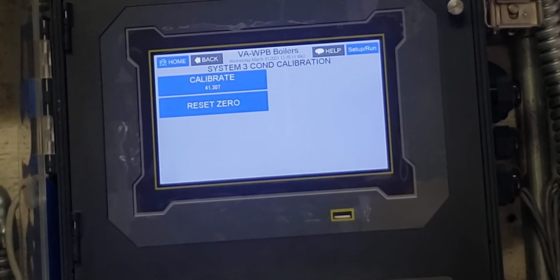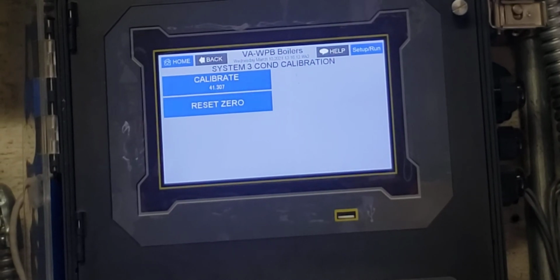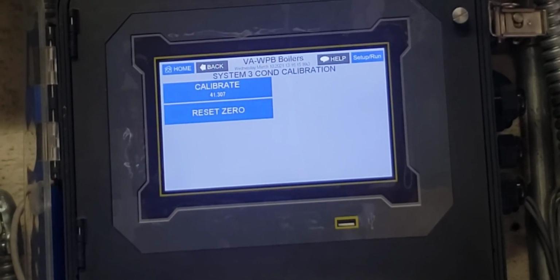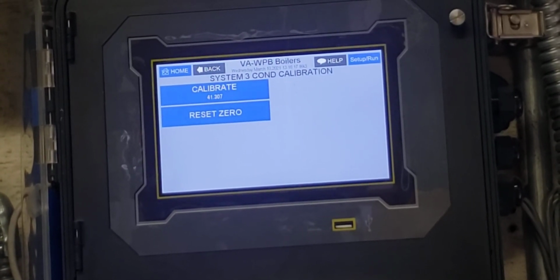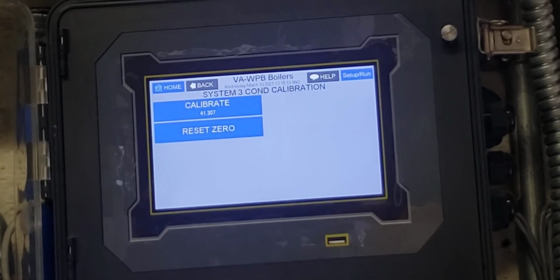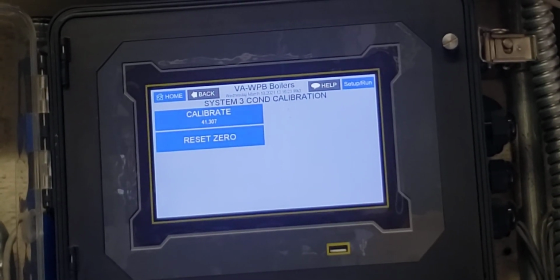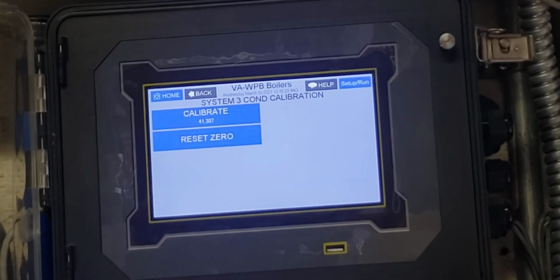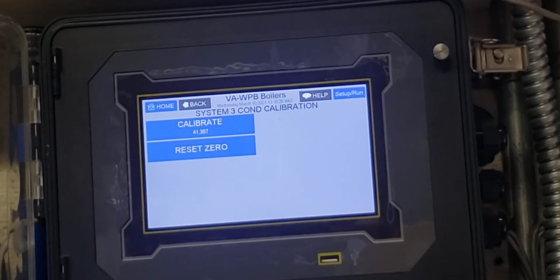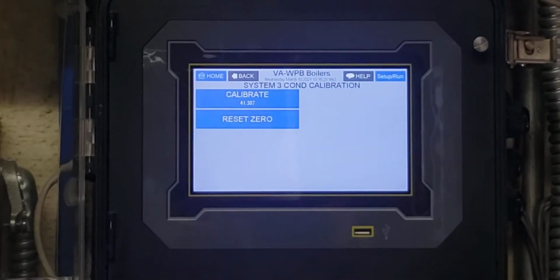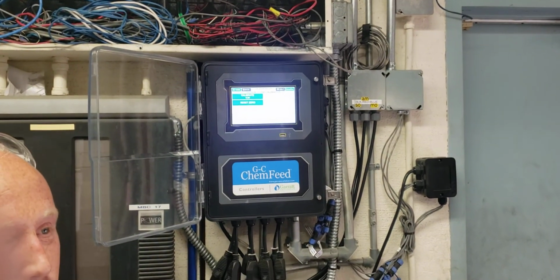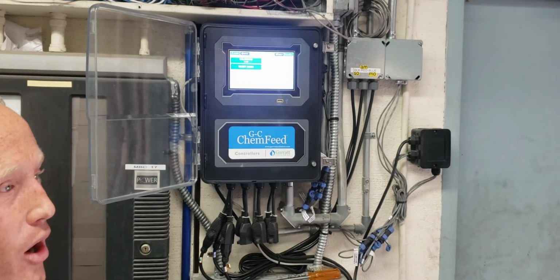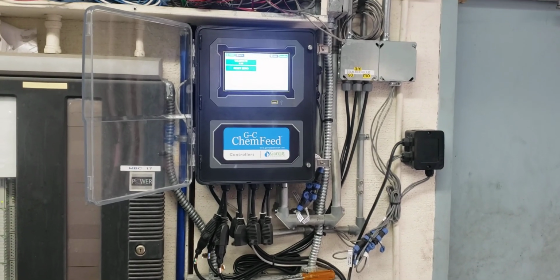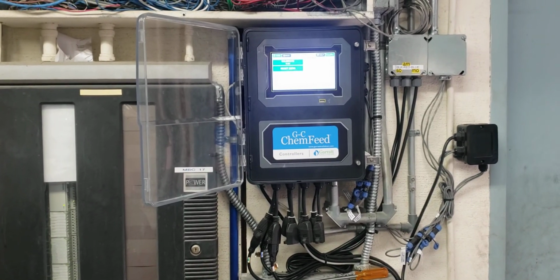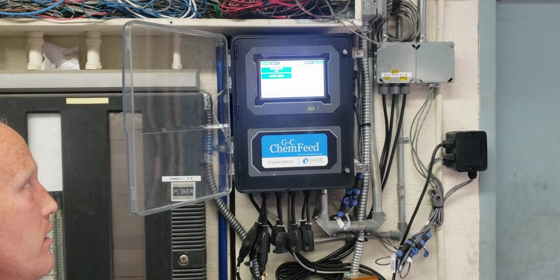Oh, okay. That's just if it's way off calibration, and you do a 1 point and it just won't get there, then at that point you take it out, clean it, do a calibration to zero, and start from scratch. Now if that doesn't work and it's still messing up, you either have a wiring issue or you actually need a new probe. And those probes are good for probably about a year to 2 years, depending on the usage and the size of the boiler.